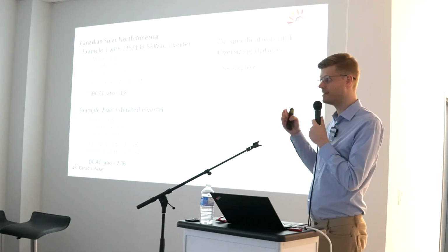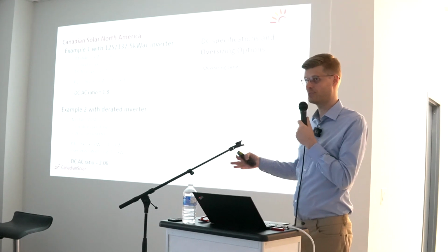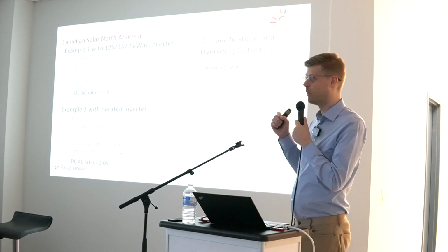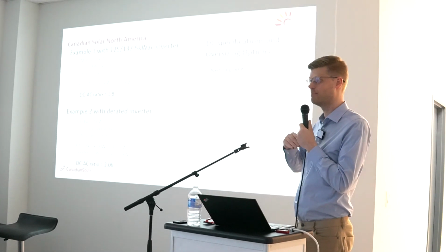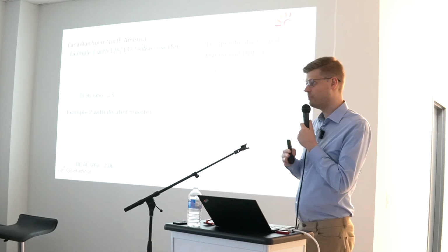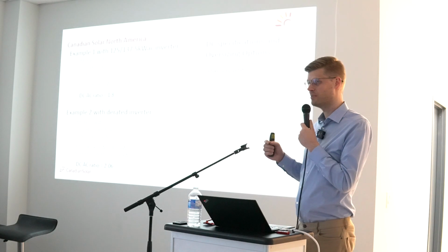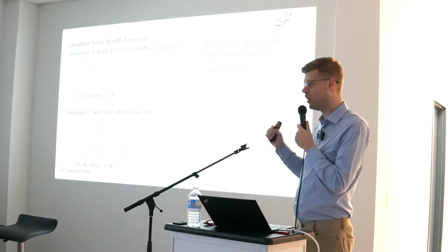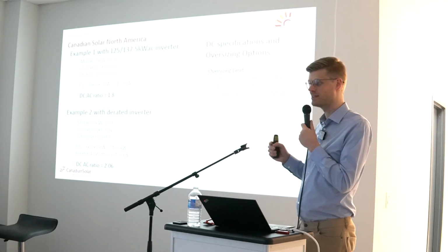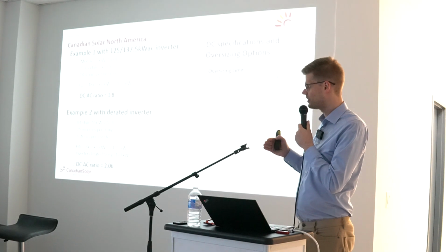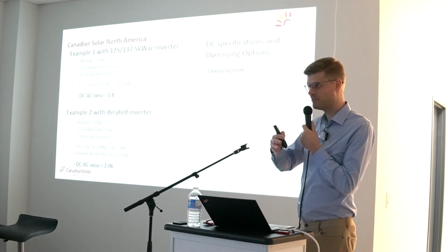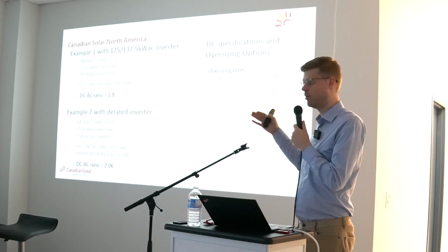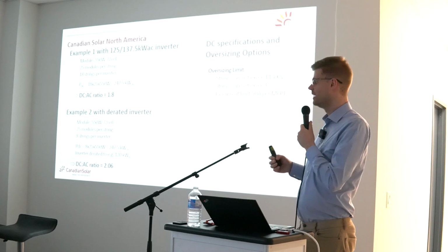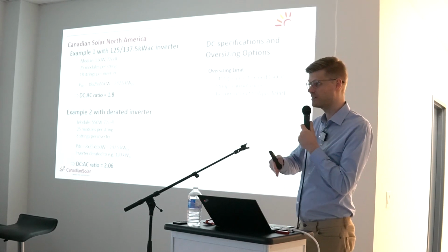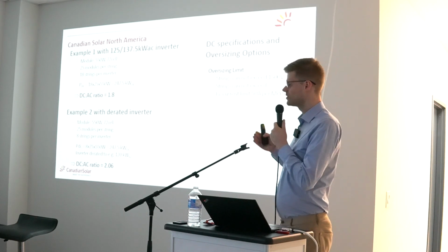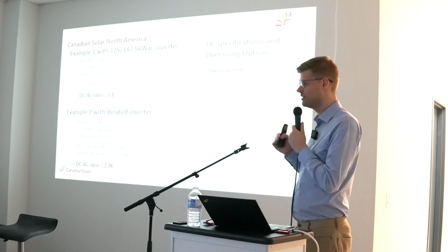At that point, you want to optimize the entire system. And you also want to optimize the system from a cost perspective. So yes, you can design the most efficient system from a technical perspective to get the most kilowatt hours out of it. That's one part. But today, more important is how can a customer or a solar installer achieve a system that has the lowest cost per kilowatt hour? And the lowest cost per kilowatt hour is, if you look into the entire system, how many kilowatt hours are you producing with a given DC infrastructure and the AC connection, your transformer, your cables, your breaker panels, your inverter you buy. Because adding more solar only costs you the solar panels, the racking system, and the labor. Everything else stays the same. And this way you can calculate multiple examples at what sweet spot you get the best bang for your buck.